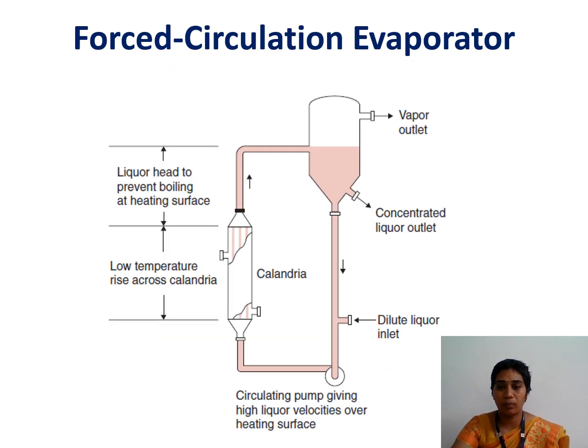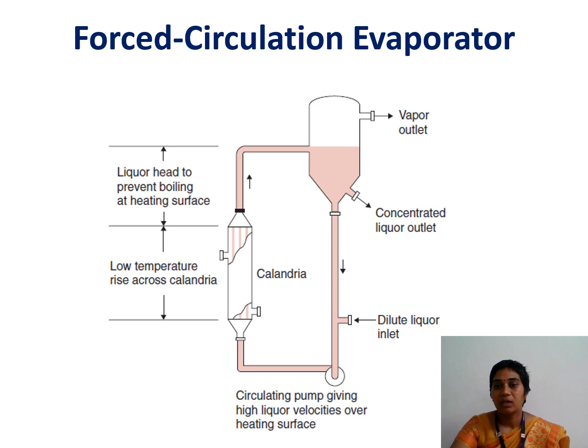Next is the forced circulation evaporator. In the previous cases, the flow of material takes place naturally. In the forced circulation evaporator, the feed material is forced inside the evaporator with the help of pumps. A pump is used to circulate the juices or food materials inside the tubes. After concentration, the product is transferred to the calandria section. If further concentration is needed, the material is recirculated through the evaporator until the desired concentration is reached.